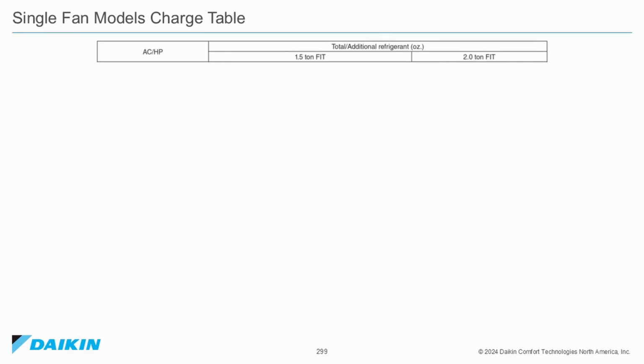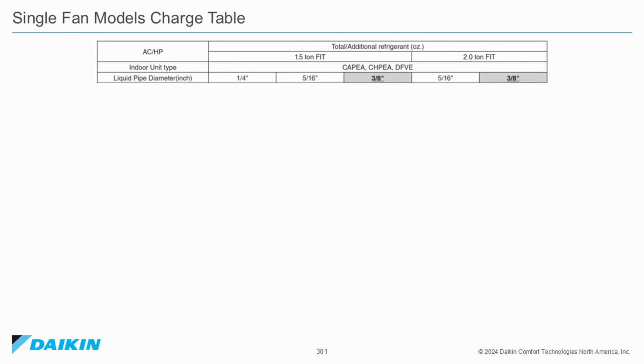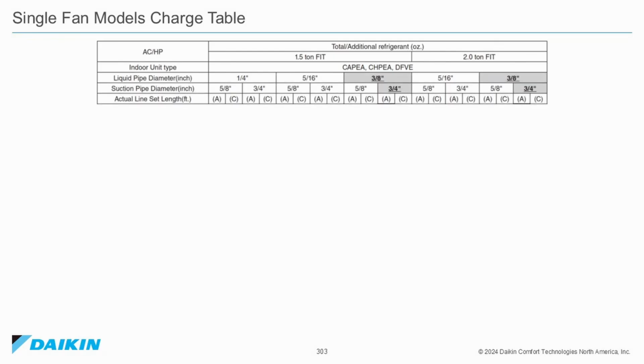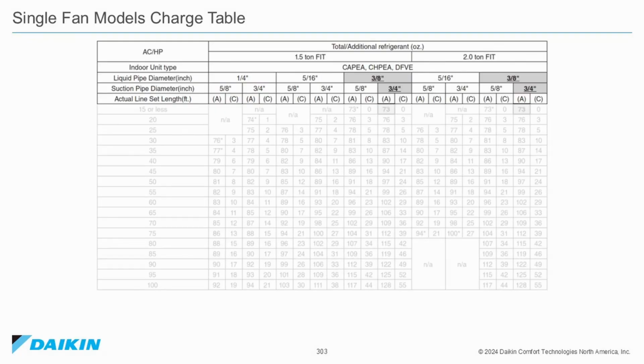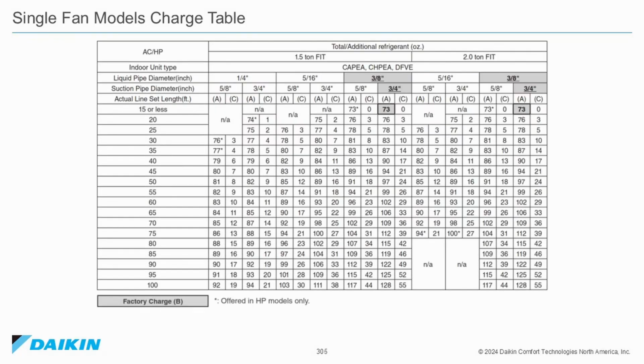On the single fan model's charge table found in the installation operation manual, look at the column for the size AC or heat pump, the indoor unit type, the liquid line diameter, the suction line diameter, and actual line set length in feet, and compare it to the chart below to determine your additional and total charge.